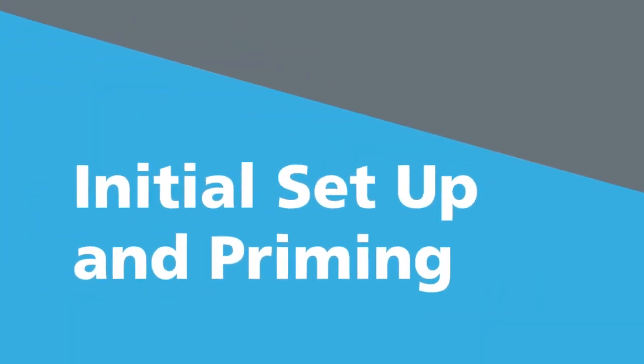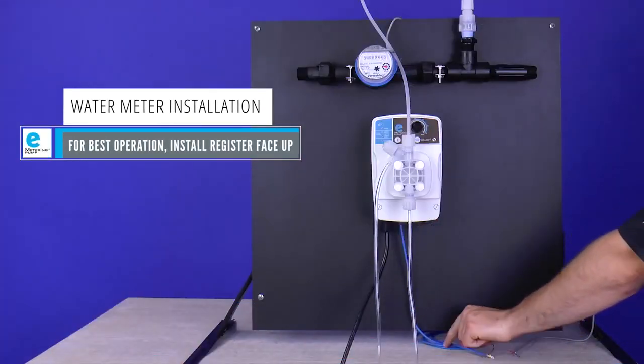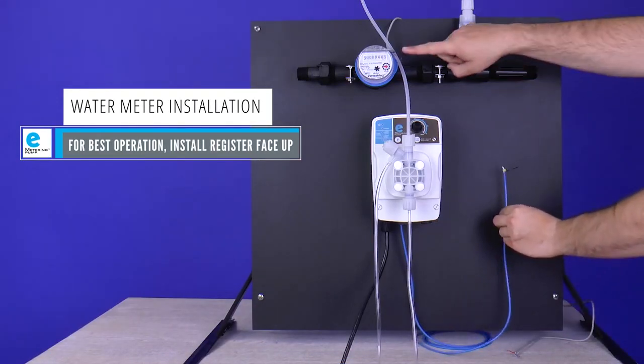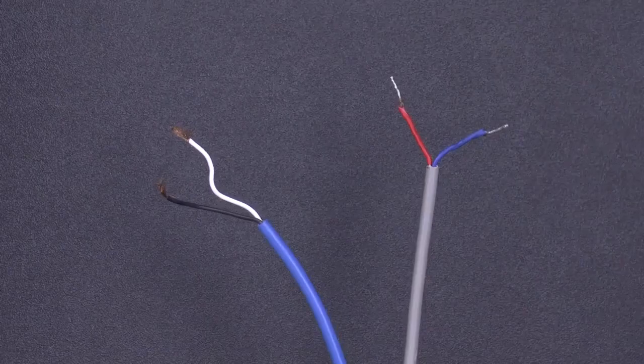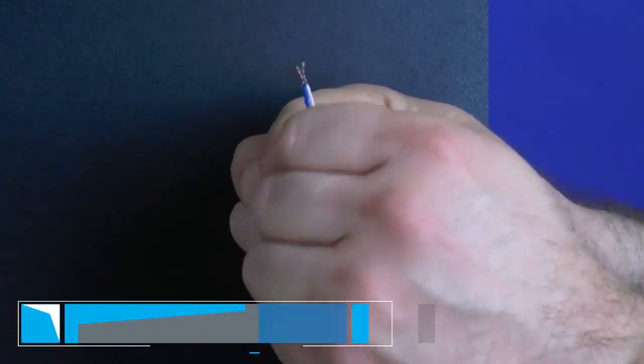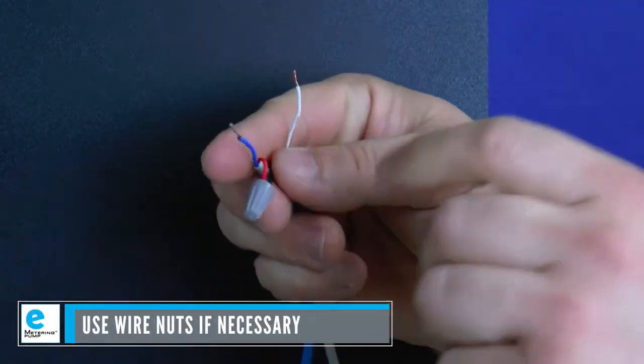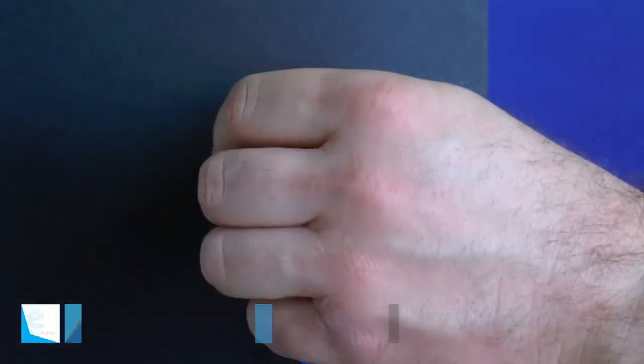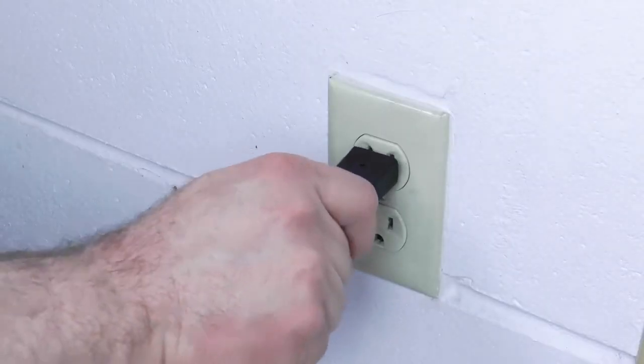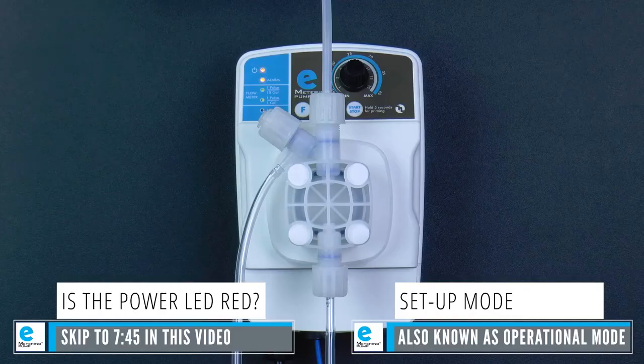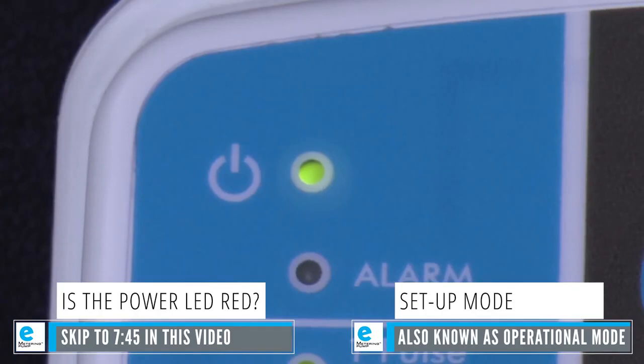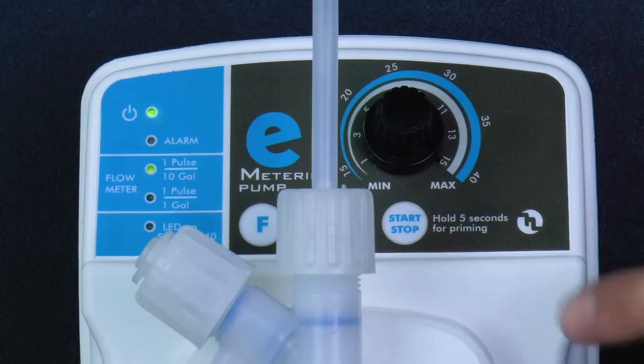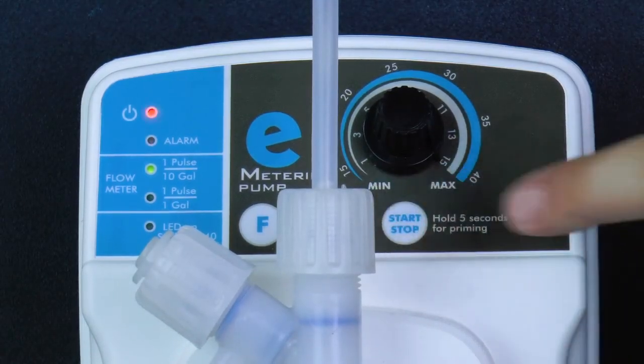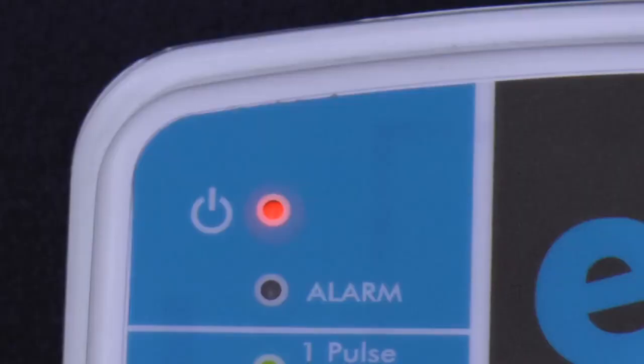Initial setup and priming. Locate the eMP metering pump lead wires as well as the water meter lead wires and connect the 2 sets of wires together. Polarity typically does not matter, but if it does, the white wire of the eMP is positive. Connect the eMP metering pump to the power supply. The power LED will light up green and the pump is now in setup mode. Press the start-stop button once and the power LED will light up red. The pump is now in standby mode.